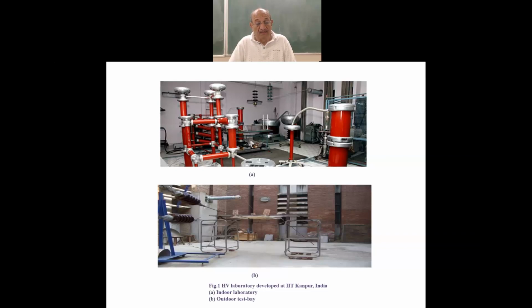And all these high voltages cater to the need of any kind of experimental work required up to 66 kV rated voltage. 66 kV rated voltage comes today as part of the distribution network of power. Transmission is at higher voltages. So for all distribution network rated voltages, the laboratory can take care.